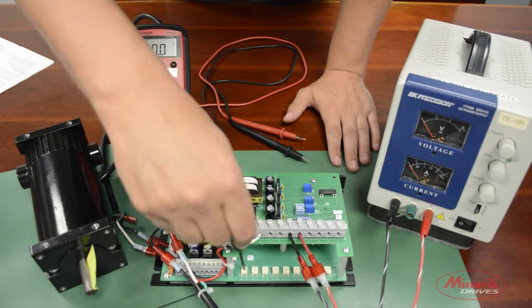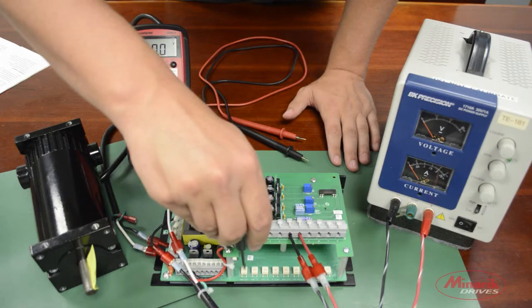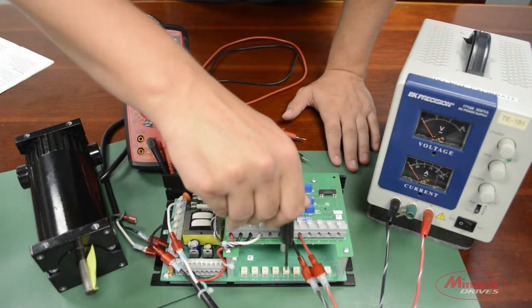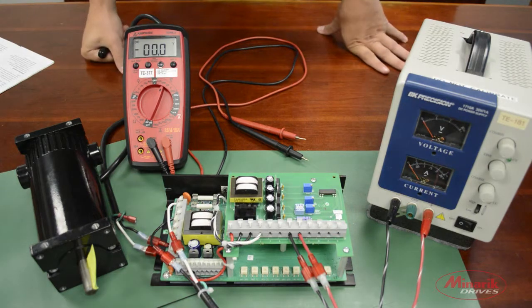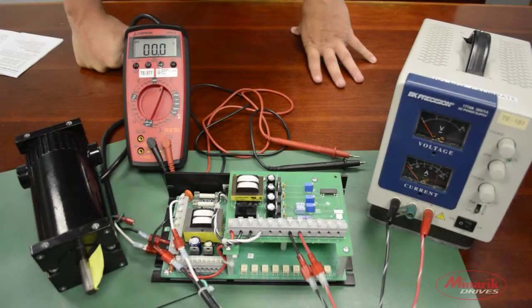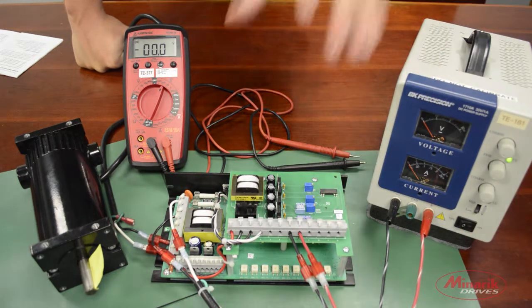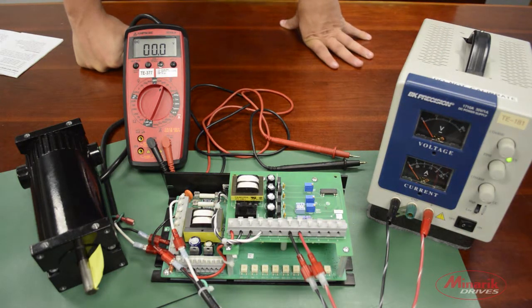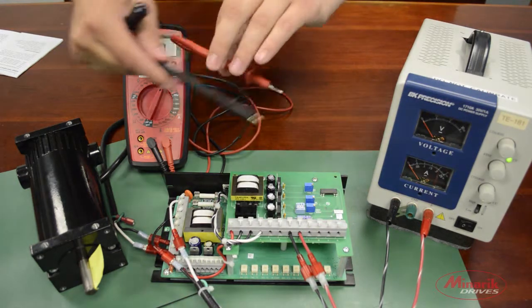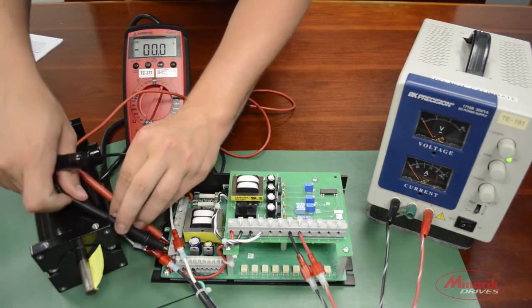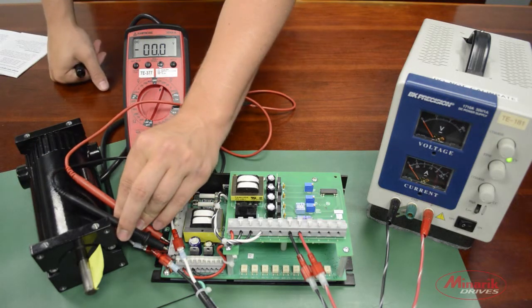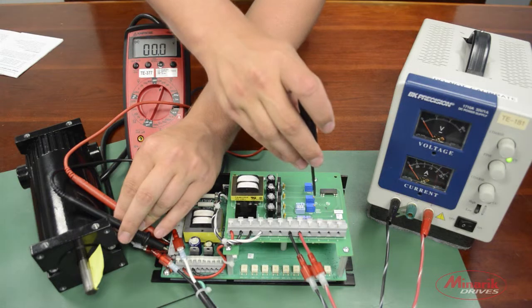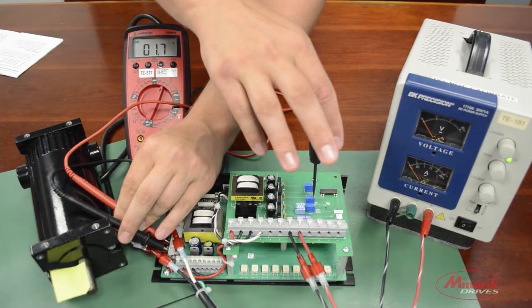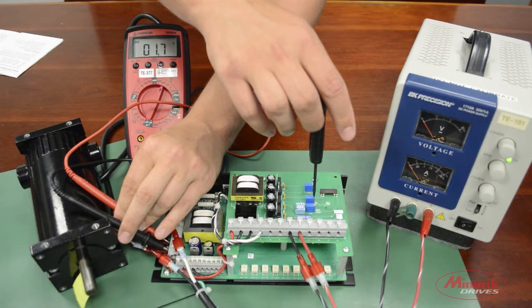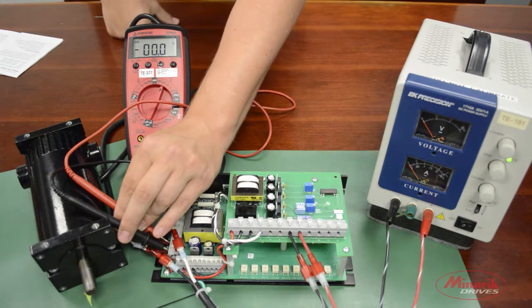The first step is to take the min speed trim pot on the drive and turn it full counterclockwise, and take the max speed trim pot and turn it full clockwise. We'll now apply power to the drive. We're now going to turn on our voltage source and apply the minimum input voltage signal we'll be using for our application. We're going to read across A1 and A2 with our multimeter and confirm we're getting 0 volts out. If we wanted a higher minimum voltage, we would just adjust the minimum out trim pot located on the isolation card. But for this demonstration, we'll be using 0 volts, like so.